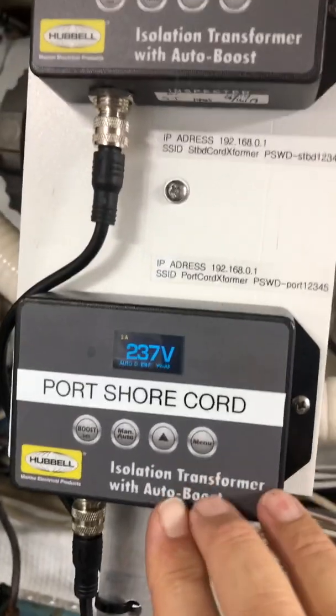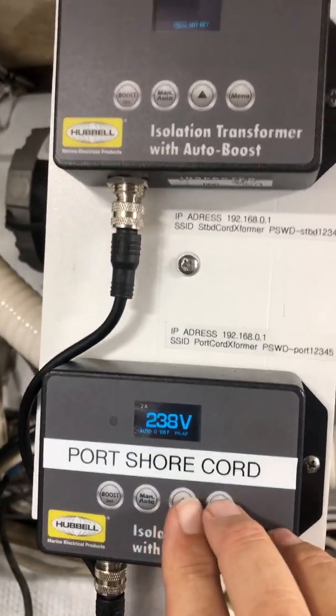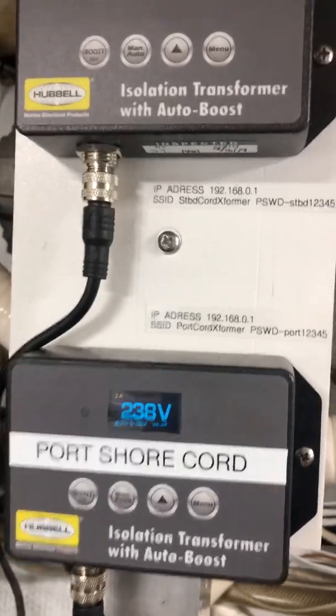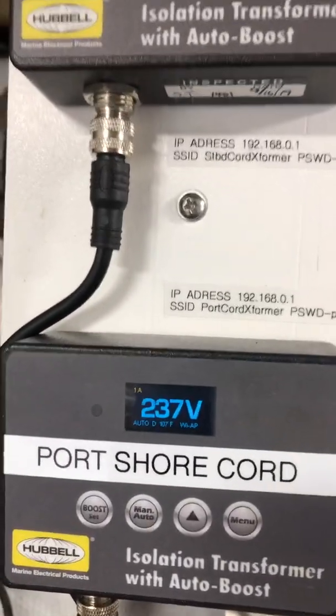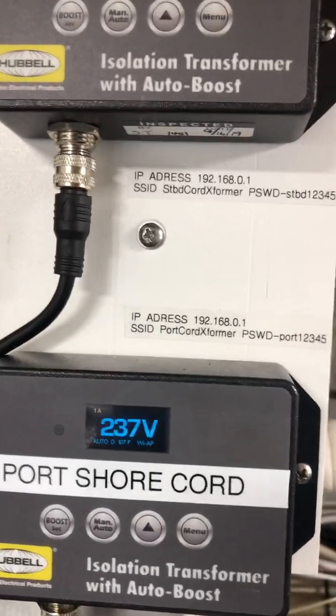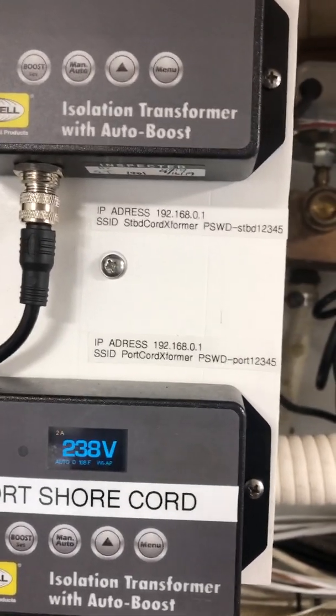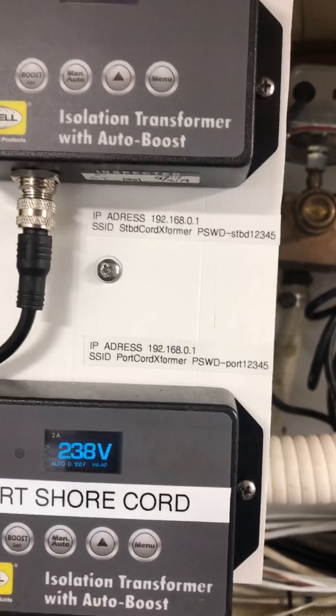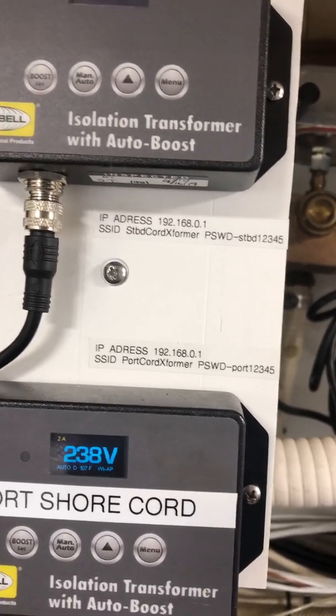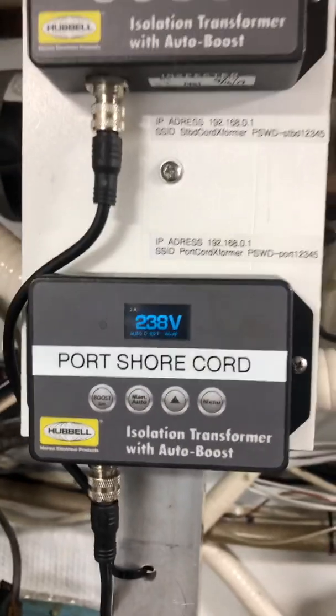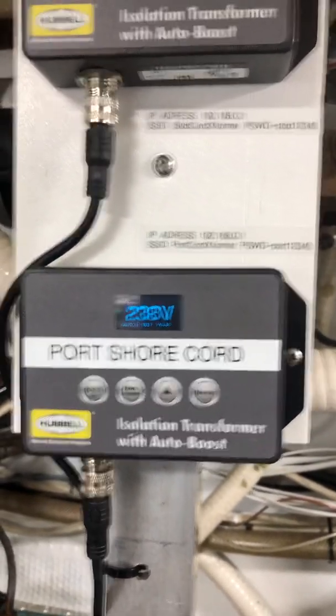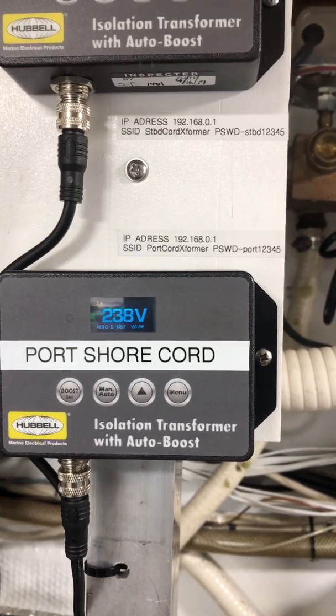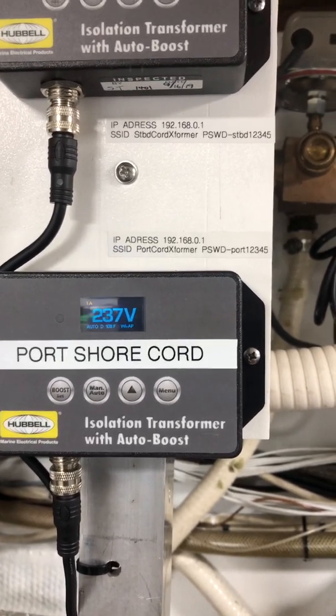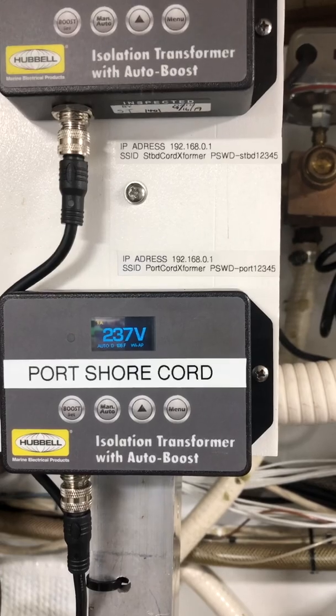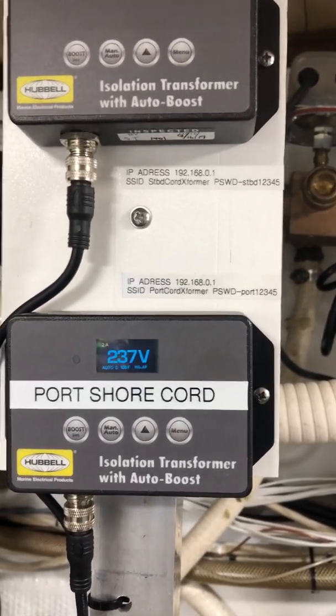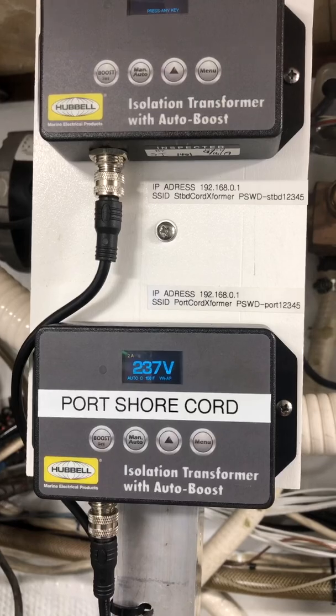One other thing is entering the programming mode. This is where you can change the operating mode of the unit from dynamic to static. Dynamic means it constantly is sampling the incoming voltage, and it will occasionally flip from boost to non-boost based on the incoming dock voltage. Static, it samples the incoming voltage only at startup when you plug the cords in and locks the unit into either boost or non-boost from that point on. I recommend you operate it in the dynamic mode.